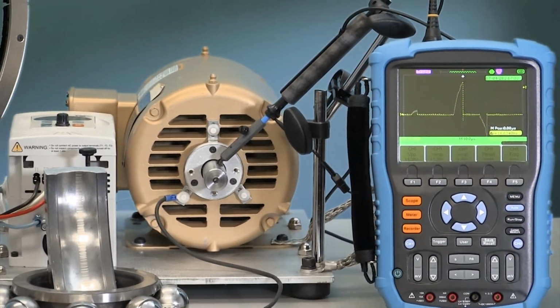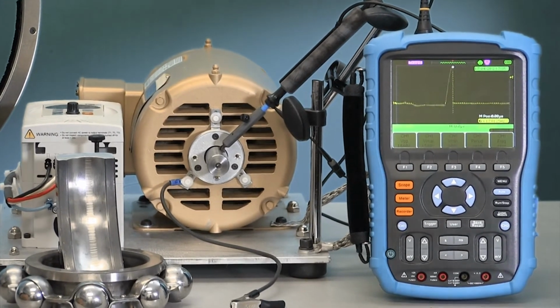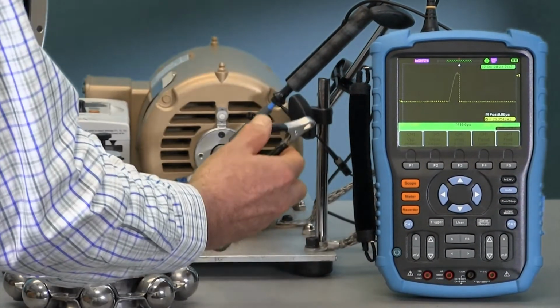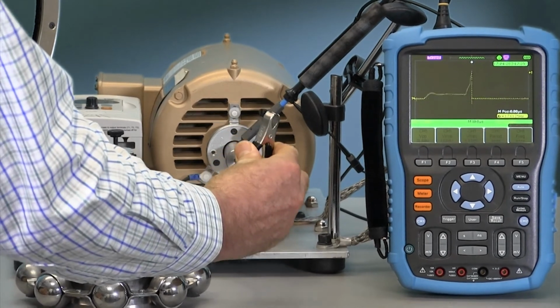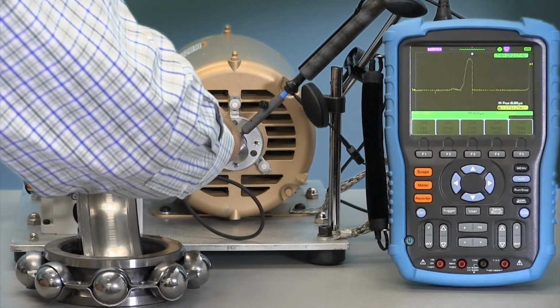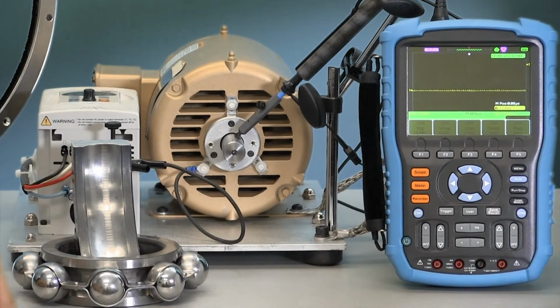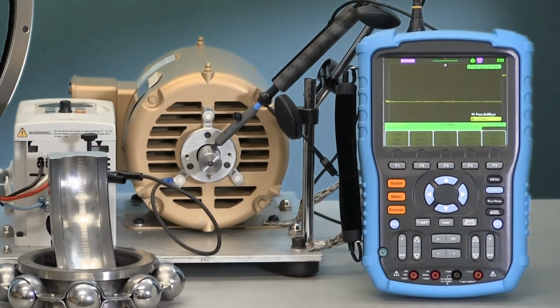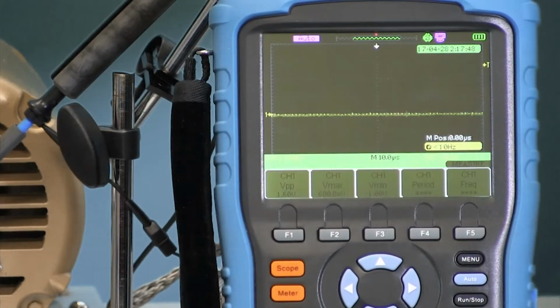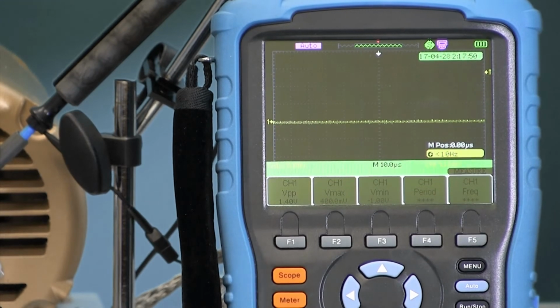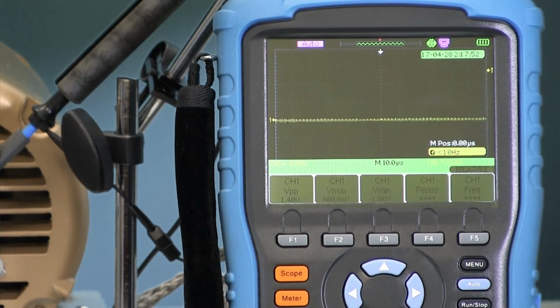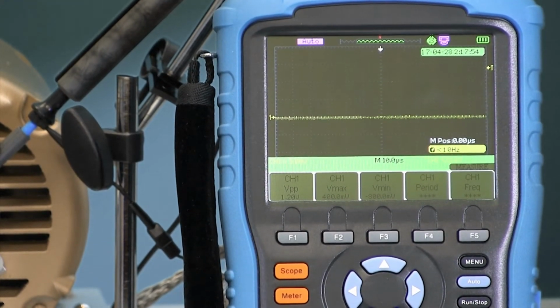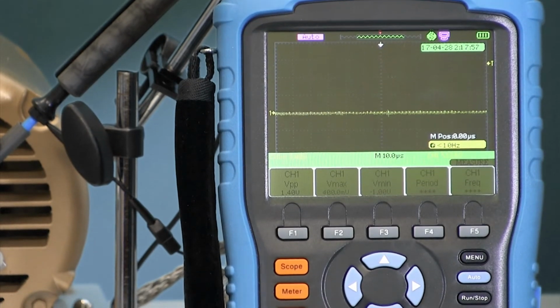Now what we want to do is connect the shaft to ground. So I'm going to take the ground wire from the shaft grounding ring and connect it to ground. And you can see when I do that, all of the voltage that was on the shaft goes away. So right now, the motor's bearings are protected by the shaft grounding ring, which has conductive microfibers which bleed any voltages away from the bearings to ground.